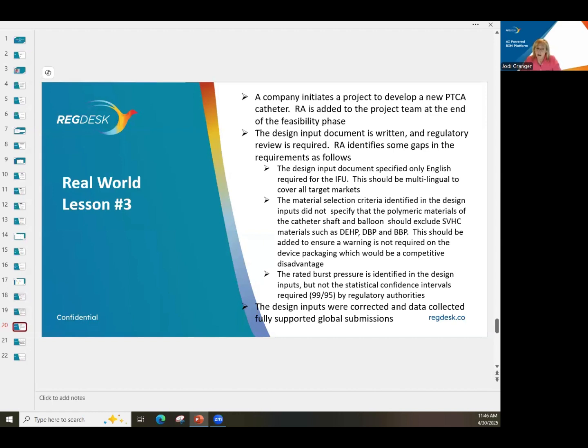The second thing that was identified was material selection. The design input document did not clearly state that substances of very high concern should be excluded. Otherwise, you would have to put a warning on the product, which your competitors do not have, and that warning would end up giving you a competitive disadvantage. By building in a requirement in your design input document related to those substances of very high concern, they were able to avoid having to put that warning in place. The last gap that was identified was that the rated burst pressure was available in the document, but it did not list the statistical confidence intervals that were required by regulatory authorities. So RA was able to point this out, and it was incorporated.